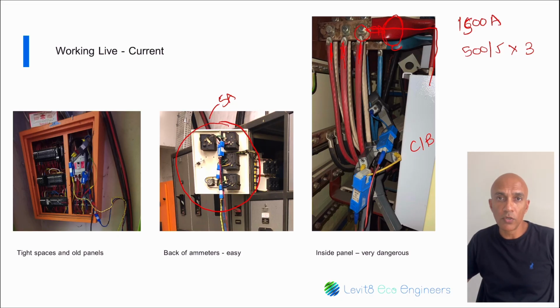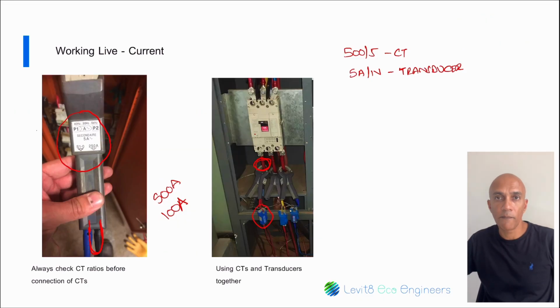So it's important to note that you may not have the direction of the current flow correct when clamping the CTs. That is okay, but you must fix this before setting the recording and leaving the site. You will fix this by checking the displayed readings on your instrument. We will cover this in the next section when configuring the setup.